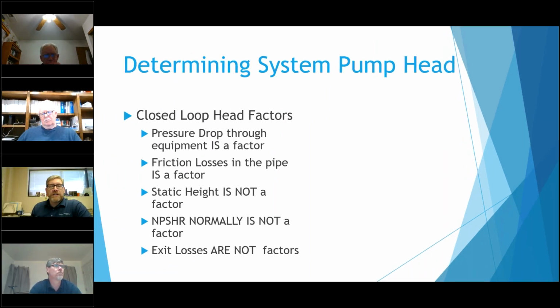The reason is, as the pump circulates that water, there's water at the top already, so that water's helping to push itself back down and helping the other side push back up. So it's really kind of self-sustaining each other. When you turn it off, the pipe is still filled and everything like that. So you don't have to really worry about the static height of a building when determining pump head on a closed loop system.